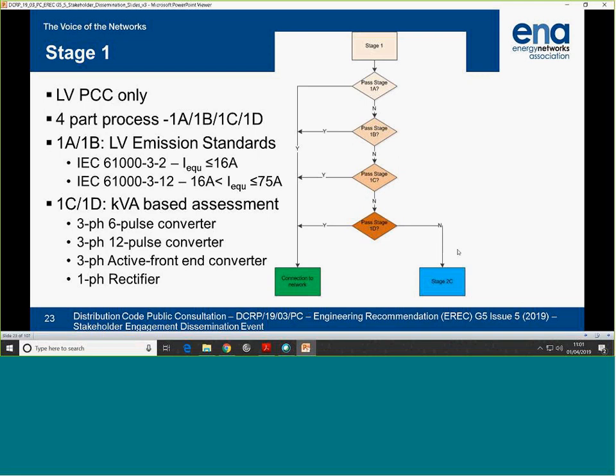A little bit more detail. Stage 1A is based on the standard 61000-3-2. That was included in the old G5/4. There's changes to that. Stage 1B is related to standard 61000-3-12. 1C is a kVA-based assessment where we cover 6 pulse, 12 pulse, active front end, and 1-phase rectifier. 1D is the variant where you're looking at the background harmonic distortion of the limiting harmonic.